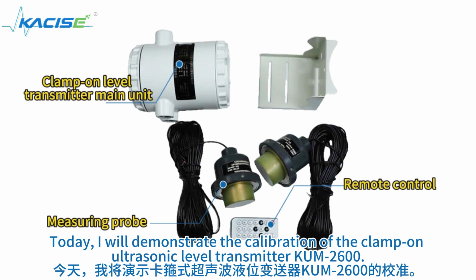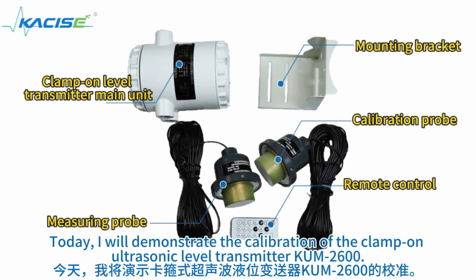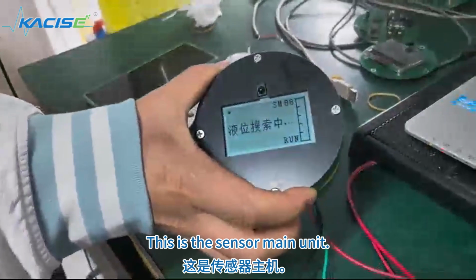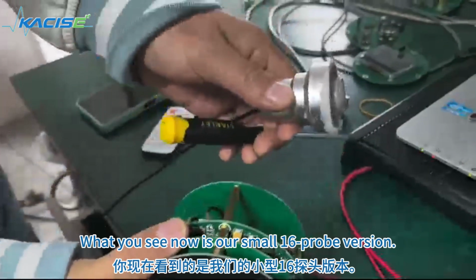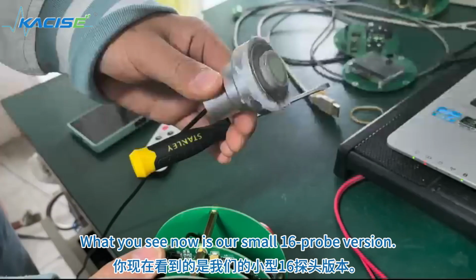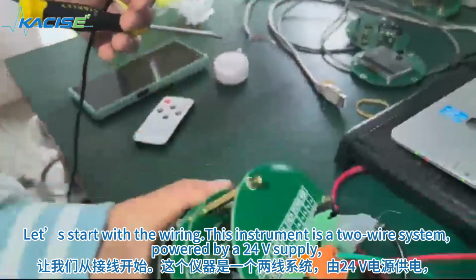Today, I will demonstrate the calibration of the Clamp-On Ultrasonic Level Transmitter KUM2600. This is the sensor main unit. What you see now is our small 16-probe version. Let's start with the wiring.